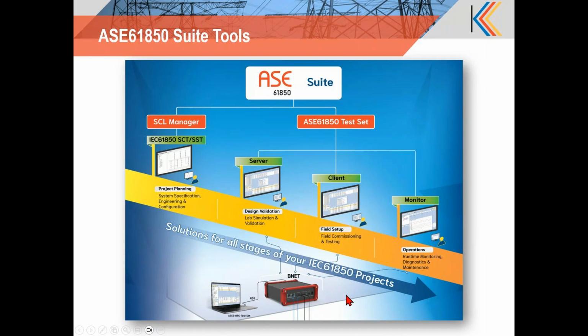And recently we launched a hardware product called the BNET. It will be an accessory to ASE61850 Test Set. This hardware works with the test set to provide you the sampled value capability. So if you want to troubleshoot the process bus, you can use this hardware and connect to the station bus and process bus and troubleshoot everything from there.